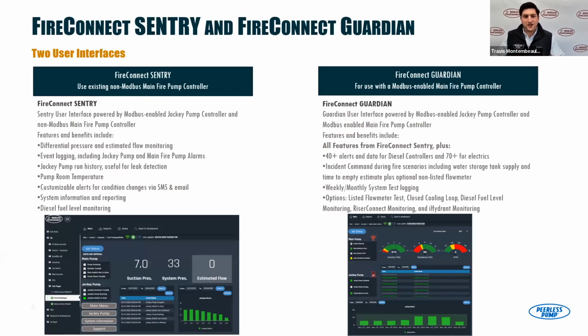And this is your first look at the UIs. So that FireConnect jockey controller will allow a retrofit customer to get a smart fire pump system by installing that jockey controller without upgrading or replacing their main fire pump controller. So we talked about being Modbus enabled for that main fire pump controller. If you've got a site, maybe your controller is 8 years old and it's still working fine, but it's not Modbus enabled, or maybe it can't be retrofit to be Modbus, we can still give you a big portion of smart systems based on that jockey controller and those inputs.